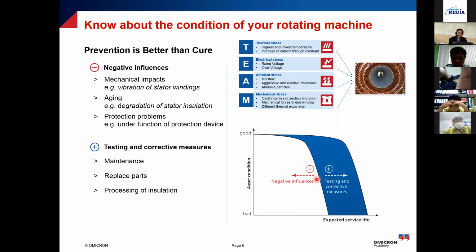So I'll share a case where we found a problem in a generator, and then immediately the testing was done. This was actually in a core. There was a fault. Immediately the fault was found, and we didn't need days to do the analysis, because in my previous company we were doing this, and we did analysis internally. So we did analysis, we found the problem, and then immediately the OEM was on site because of the major overhaul. So the OEM addressed the issue. He basically did the on-site maintenance, or on-site repair, I should say, and rectified the fault. So it can be done, and therefore the life can be improved by this.